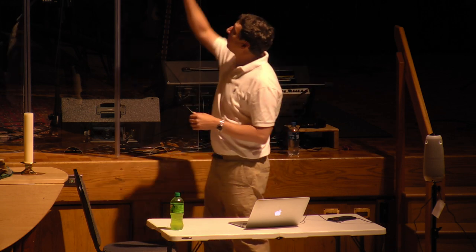Okay, so HSPF stands for Heating Seasonal Performance Factor, and this is a measure of heating efficiency. So the higher the HSPF, just like with SEER, the more efficient the unit. Now this one I've circled here is 11. That's pretty stellar too. So it's doing not only the work in the summer, it's doing the work in the winter. The minimum in 2023 for HSPF will increase to 8.8 from, I think, 8.2 now.